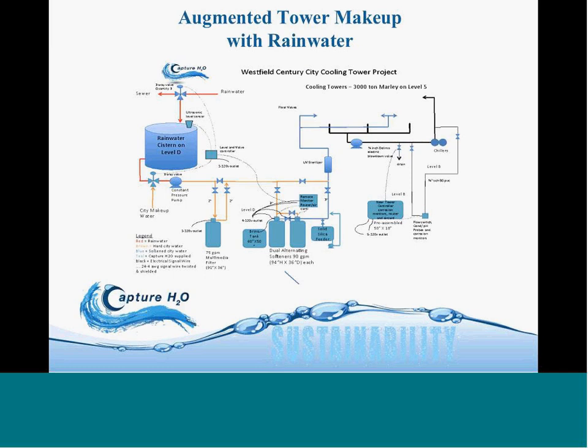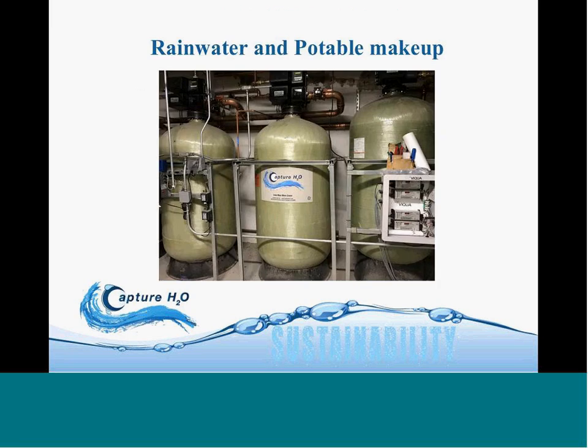We also have a city water backup. So say there's no rainwater, it'll make up automatically with city water. Water comes out of that tank and we repressurize it through some pumps. We go through a multimedia filter which removes suspended solids from that water. Then we go through the pre-treatment system, basically softening that water. It goes through a UV sterilizer, mainly for E. coli control of that rainwater, and into the cooling towers. On the cooling towers, we have remote monitoring and corrosion monitoring.